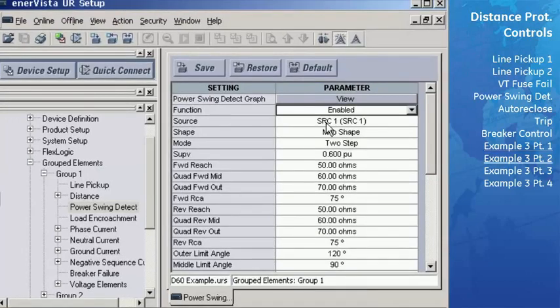For this example, we'll use the Mho shape with 2 steps, so keep shape as Mho shape and the mode field as 2-step, since we're only going to use the power swing blocking function. Keep the current supervision field at 0.6 per unit, since the currents will be much larger during a power swing.